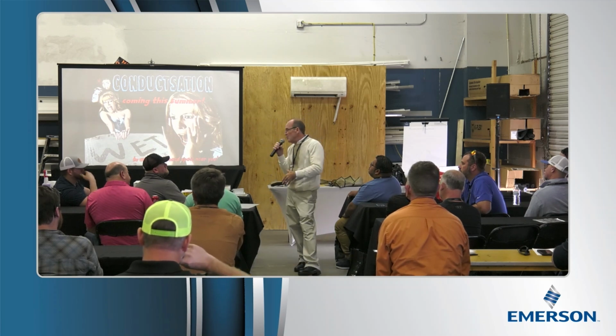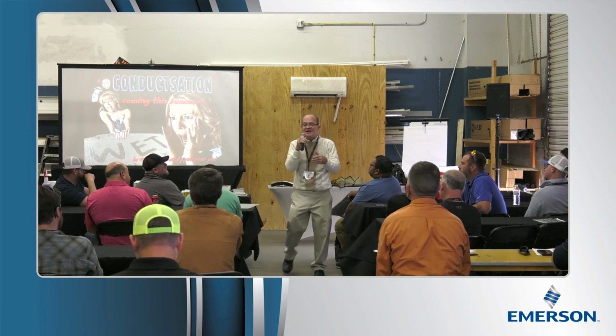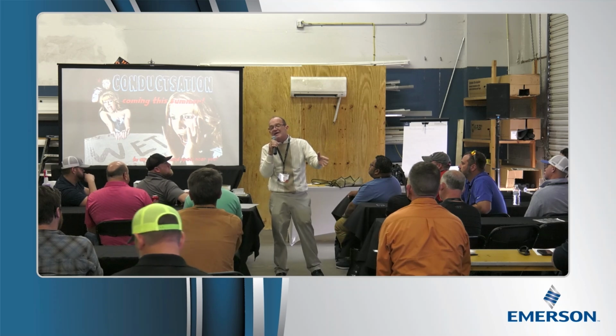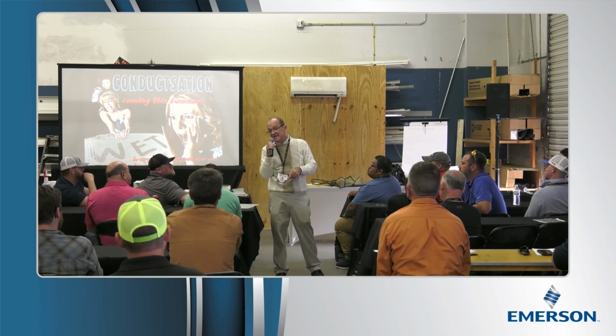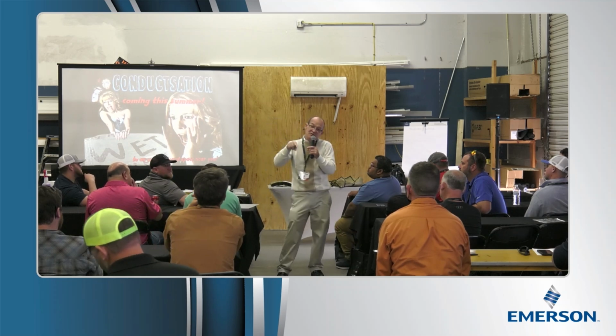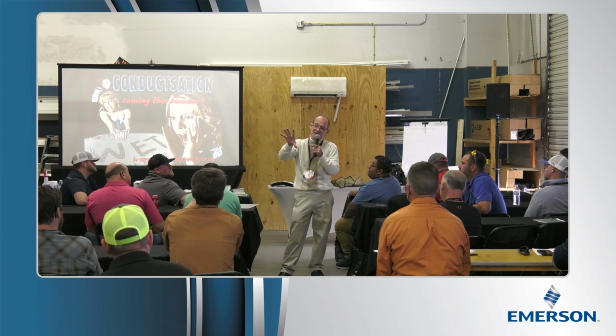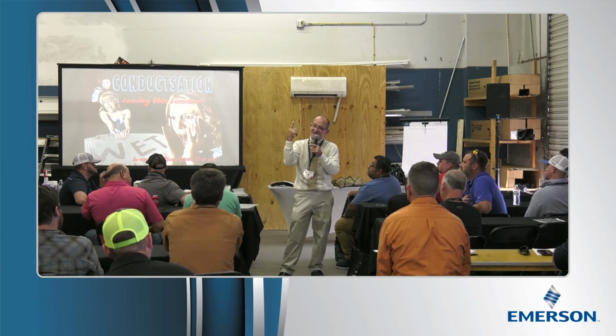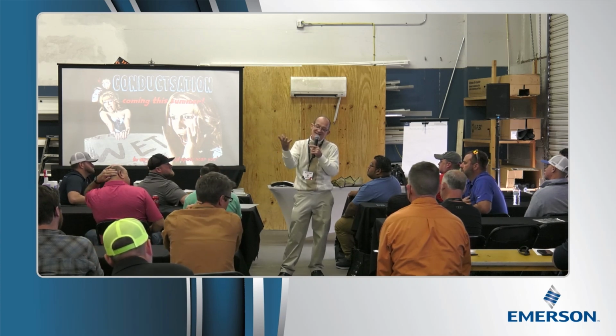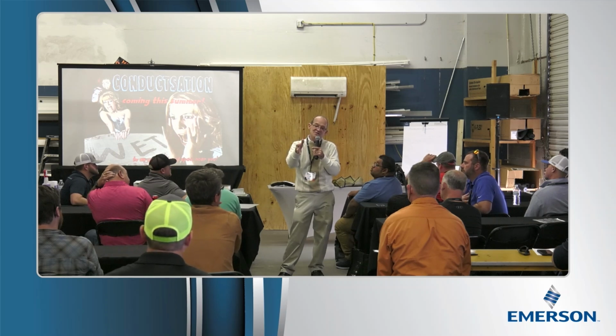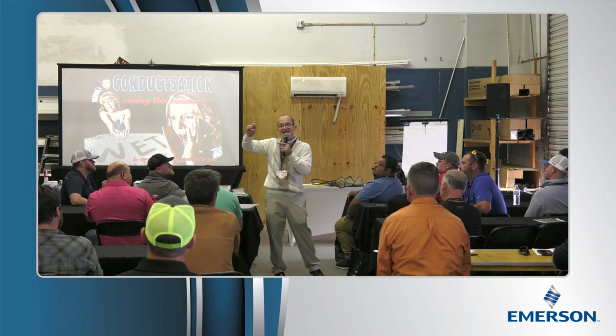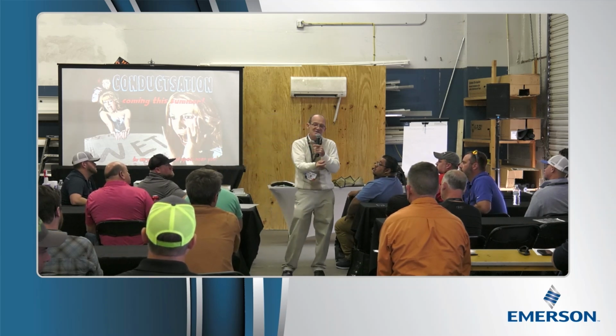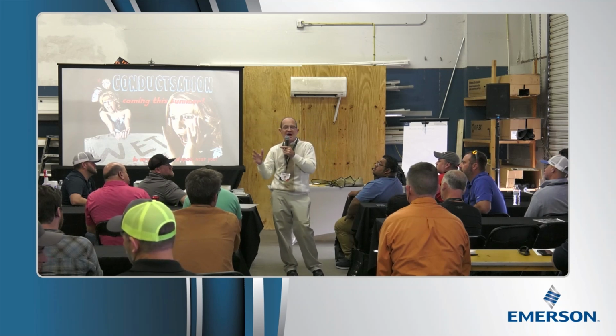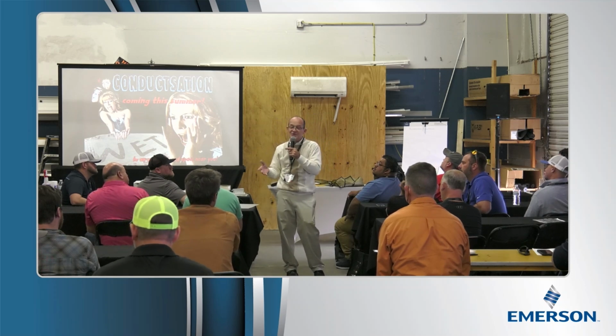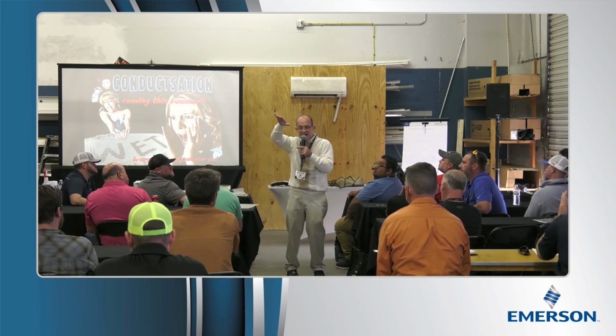But when it comes to how it got wet in this air handler, it can be bypass. Remember we talked about when you leak into the cabinet, that air doesn't go through the coil, it doesn't get filtered. So if you wanted to reduce that, a simple piece of tape, taping the panel covers, does more good than any high-tech solution you could come up with. You just have, and now the other one is bypass.